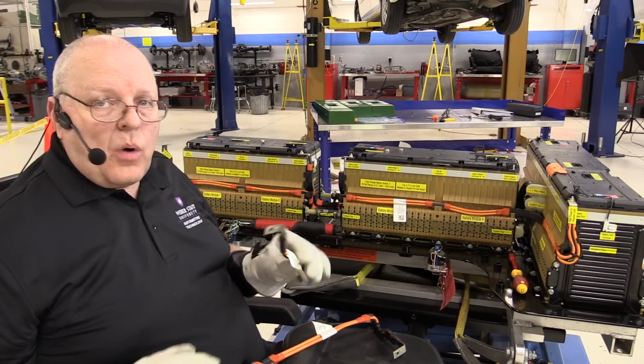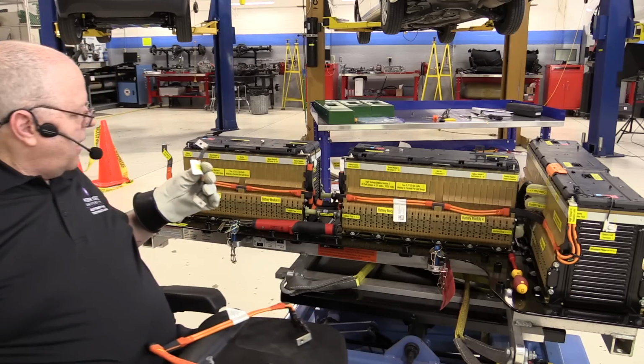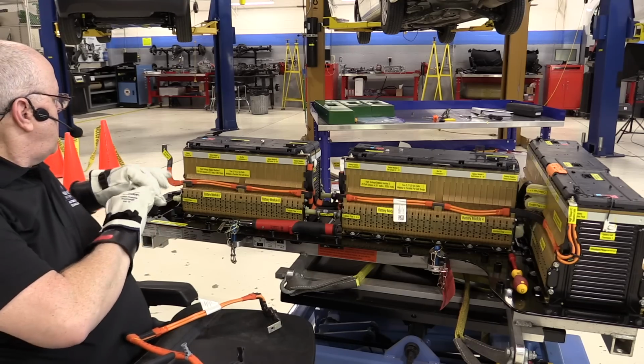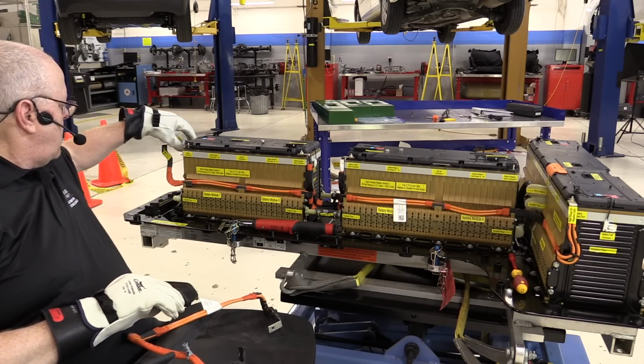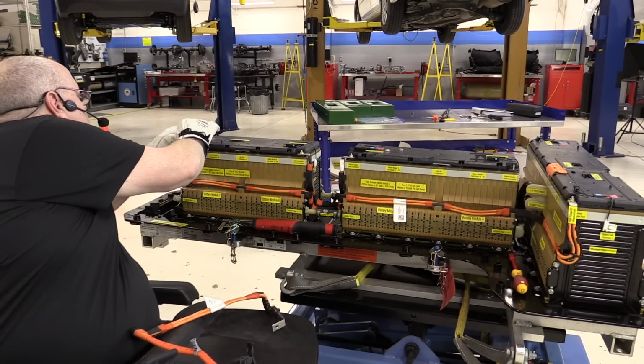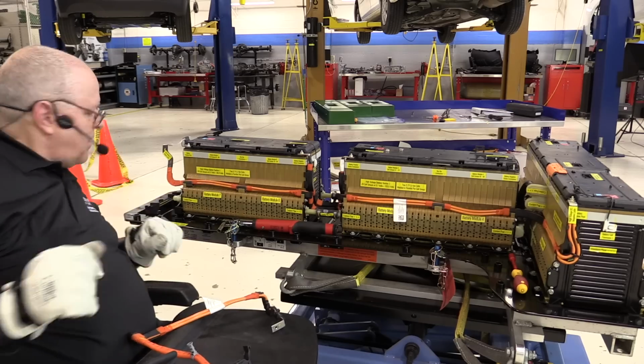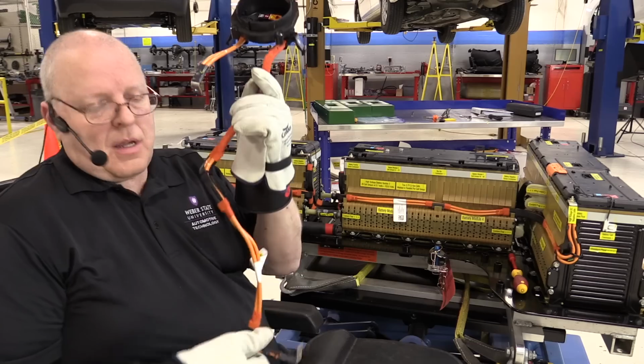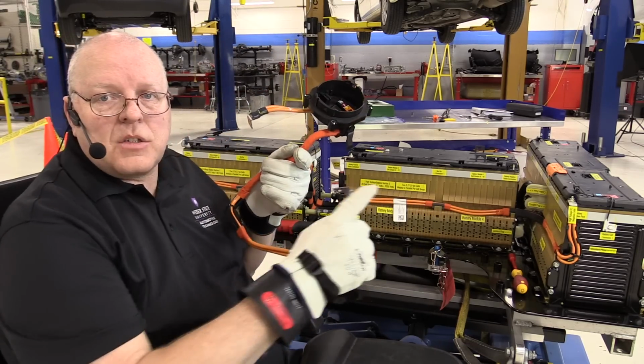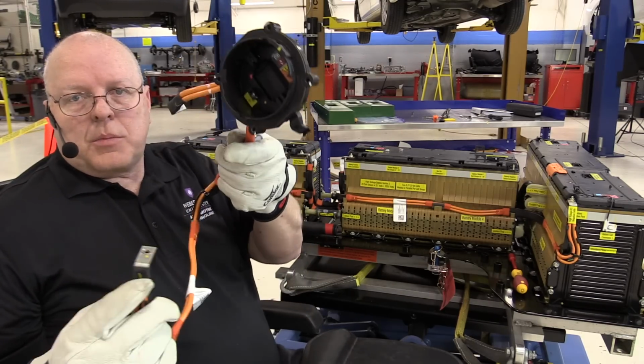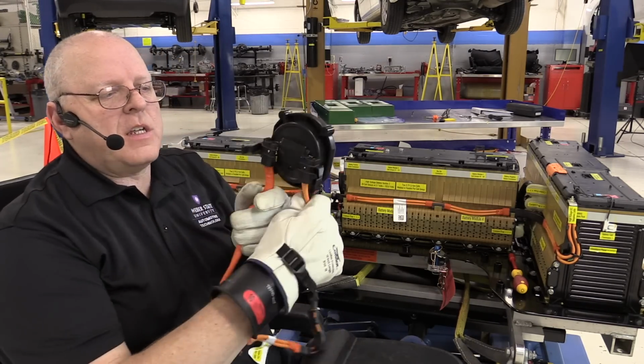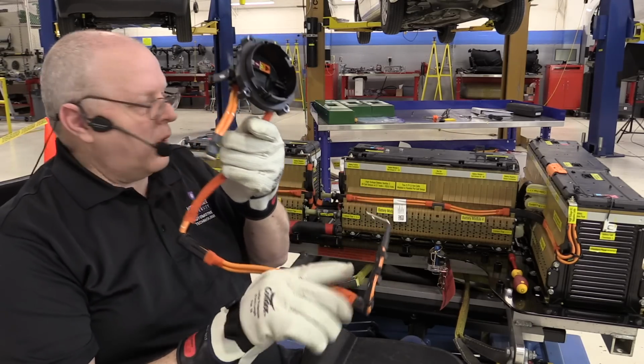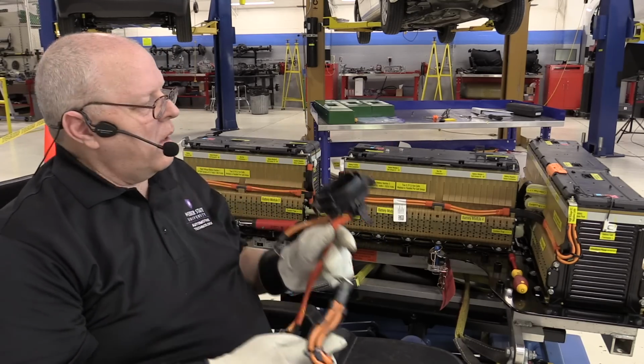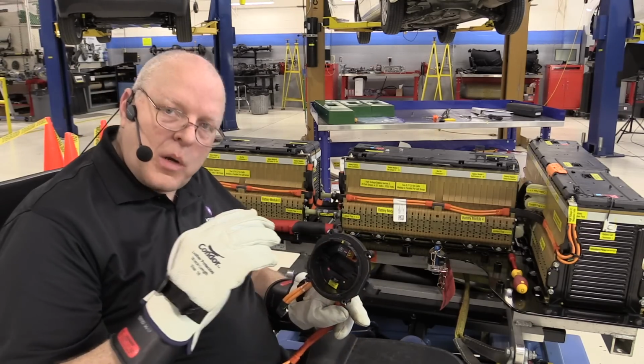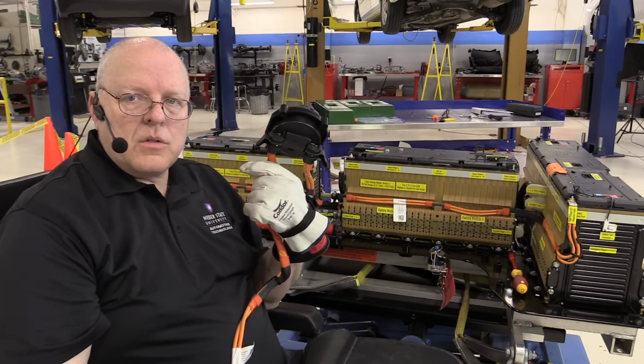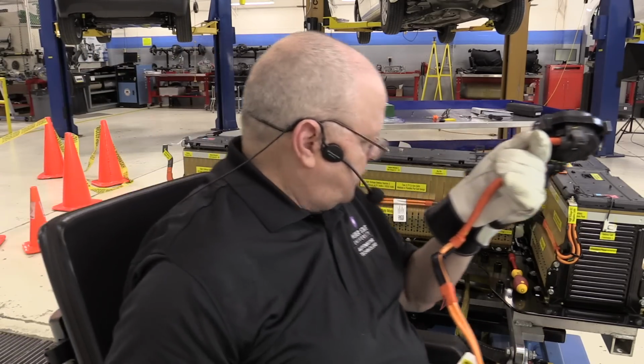Let's do all the torquing at once. Here's our positive cable, and it's going to go from our positive post up here to the contactors once we get those installed. And then this is the last series cable that connects section 3, the back section, to section 2. Normally this would just be a piece of wire, but we have a service plug here that physically disconnects these two wires, so this is an open circuit. When I bolt this up here, there will be no electrical current possibility going through here until I put in the service plug that connects these two circuits back together. So let's get it over here.